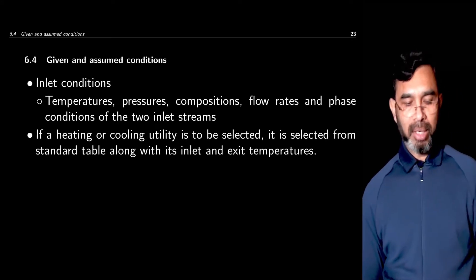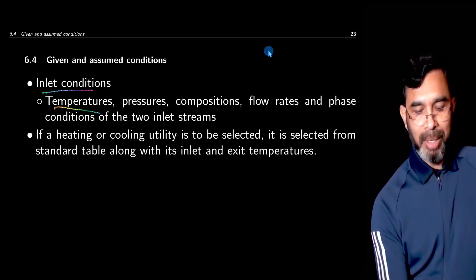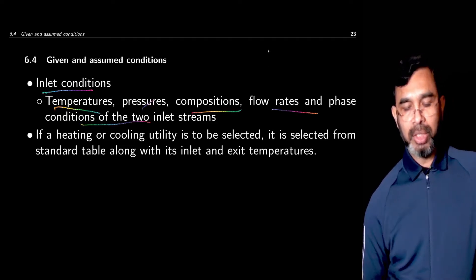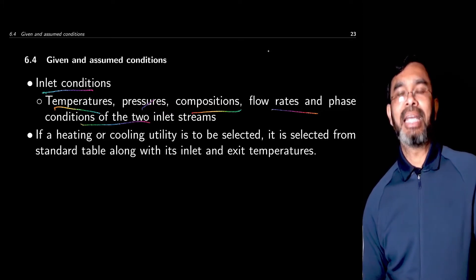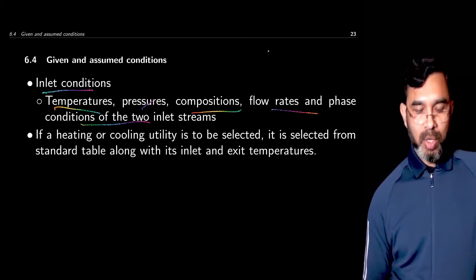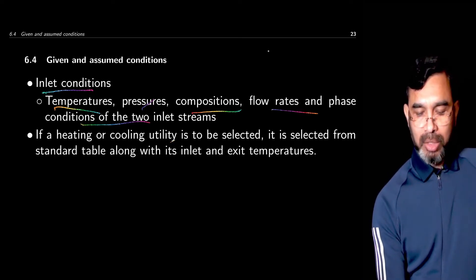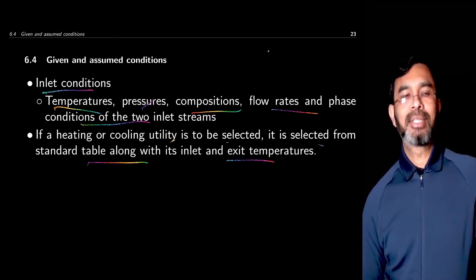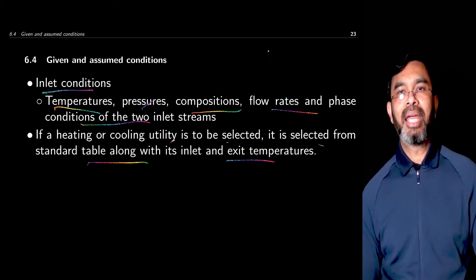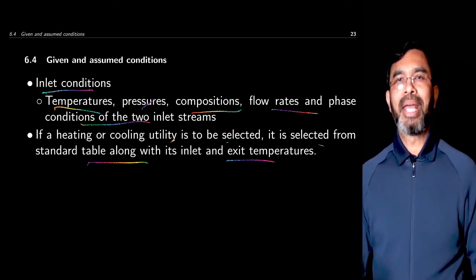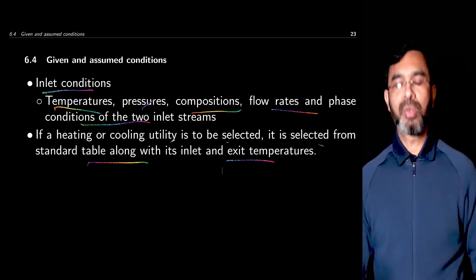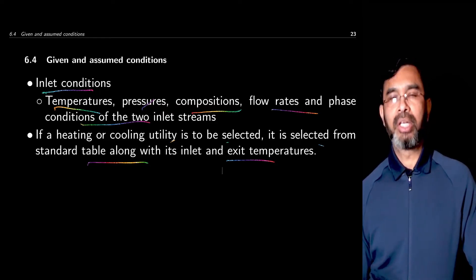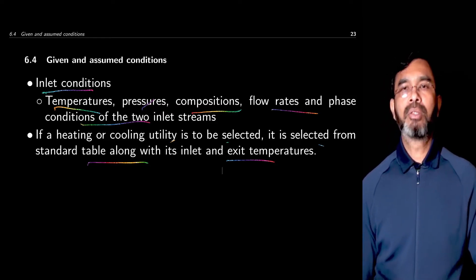Typically there are some given conditions. Inlet conditions are given — we know the temperatures, pressure, compositions, flow rates, and the phase condition of the two inlet streams. That defines the delta T as well as the heat duty. If a heating or cooling utility is to be selected, it is selected from a standard table along with inlet and exit temperatures. For example, if you are using ambient air or water from natural sources, that inlet temperature is defined, and the exit temperature may be restricted by environmental regulations.